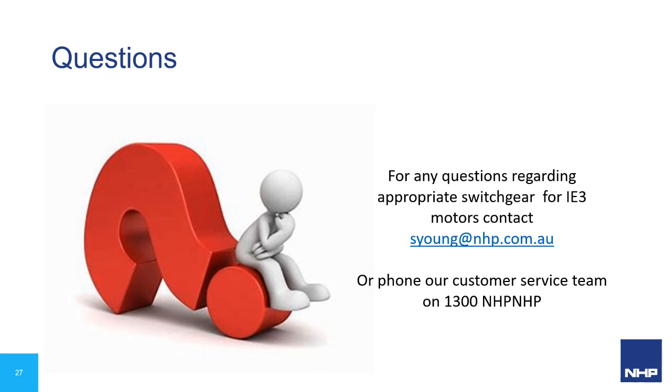Thanks for the question there, Ron. Yes, look, as I mentioned during the presentation, soft starters can be used. However, they are load dependent, and the reason for that is they are not like a VSD. They are a reduced voltage method, pulse width modulator reduced voltage method of starting the motor. So effectively, it cannot increase the motor's torque beyond the rules of reduced voltage. The torque available reduces to the square of the decrease in the voltage.